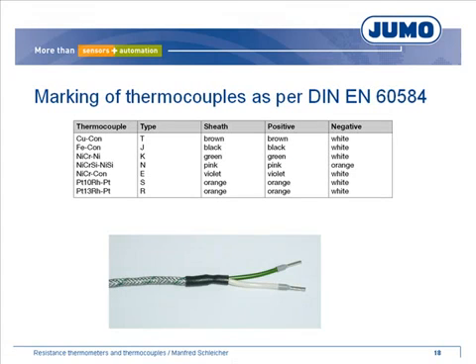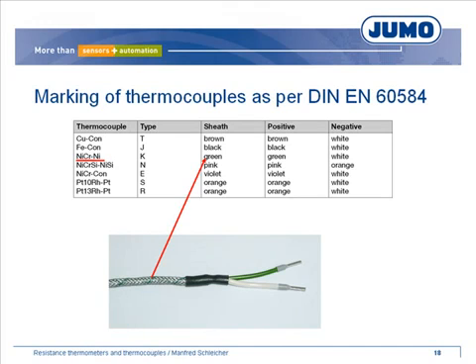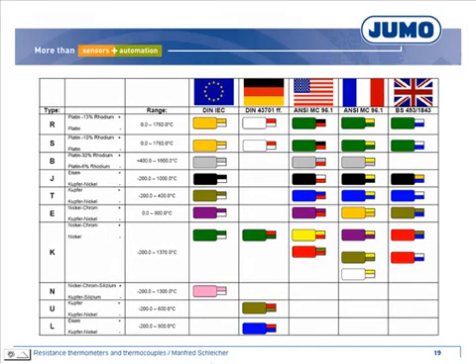When thermocouples are manufactured to DIN EN 60584, the color of the compensation cables and the limbs enables you to identify the kind of thermocouple. For example, the sheath of the often-used thermocouple nickel-chrome-nickel type K has a green marking. The positive terminal is green and the negative terminal is white. This chart also shows the color coding as per different international standards.